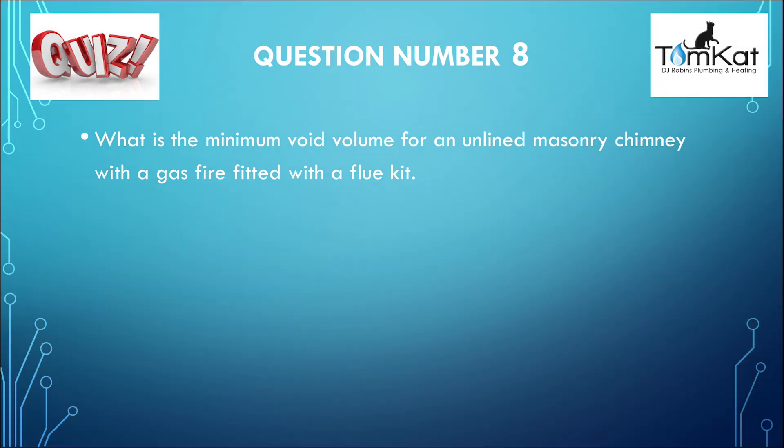Now the answer for question number eight: what is the minimum void volume for an unlined masonry chimney with a gas fire fitted with a flue kit? The answer was C — 12 decimetres cubed. That was the answer for number eight.